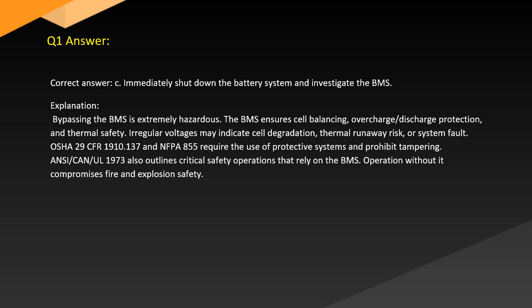Answer. Correct answer. C. Immediately shut down the battery system and investigate the BMS. Explanation. Bypassing the BMS is extremely hazardous. The BMS ensures cell balancing, overcharge-discharge protection, and thermal safety. Irregular voltages may indicate cell degradation, thermal runaway risk, or system fault.